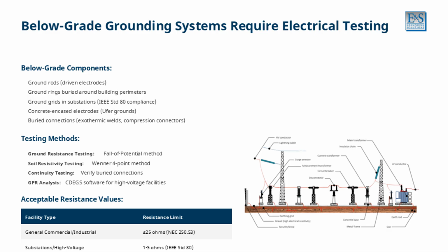Acceptable resistance values vary. General commercial and industrial facilities require 25 ohms or less per NEC 250.53. Substations and high-voltage facilities require 1 to 5 ohms per IEEE Standard 80, and telecommunications facilities require less than 5 ohms. Maintenance intervals for electrical testing. Condition 1 requires 60 months, Condition 2 requires 36 months, and Condition 3 requires 12 months.